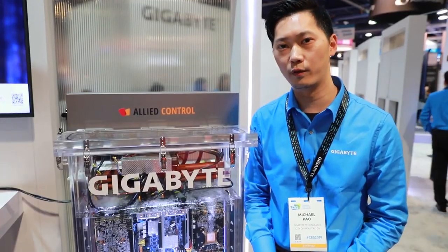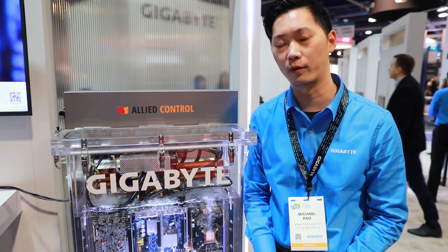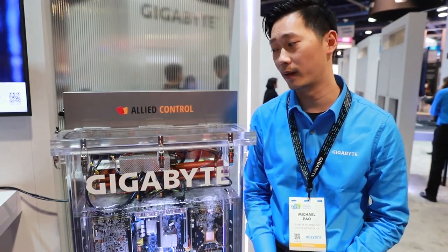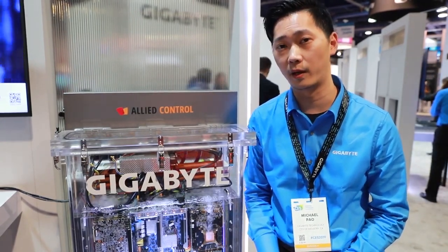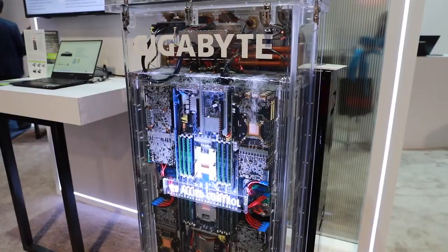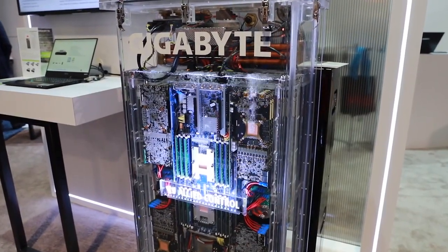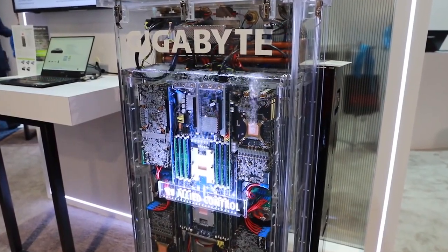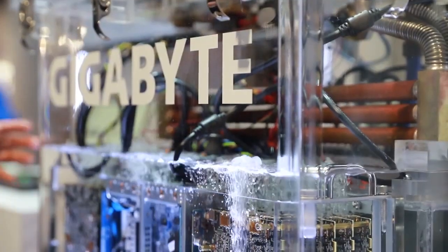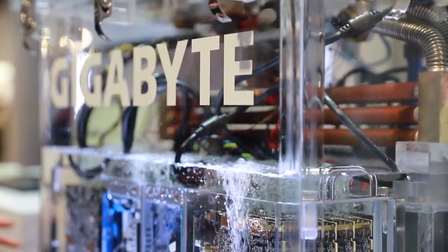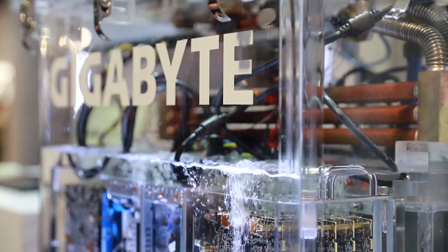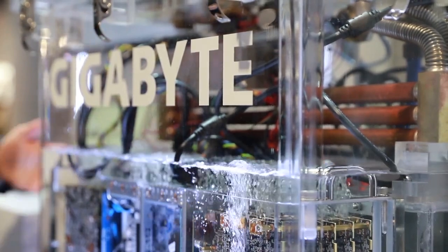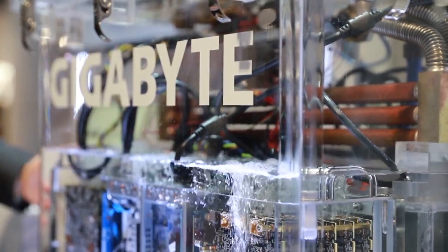We're continuously looking for better server solutions for a better future, and it's apparent that liquid cooling is a lot better at moving heat than air. This allows the CPU and GPU components to operate at temperatures a lot lower than normal air cooling, allowing them to run at greater speeds to achieve better performance while also reducing power consumption and energy bills, since we don't need fans inside the chassis.